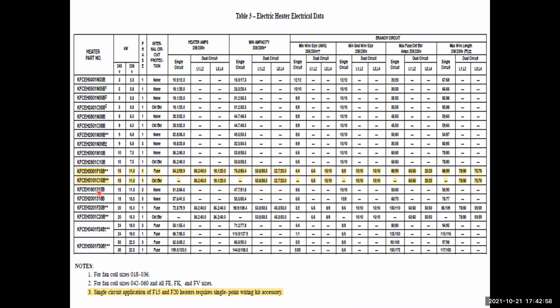You can see when we look at our spec information, when we have the breaker style and we look and see what our amp draw and what it is approved to be, there's nothing there. We come over here to a dual circuited and we're good to go with using it. So if we know that we're going to be using a 15K or 20K heater, we want to make sure that we use the fuse style of heater. And then it's also letting you know with the double asterisk that you'll need to use a single point wiring kit with it. Please use the heater package that is factory and UL listed approved for the application. Keep you out of trouble.